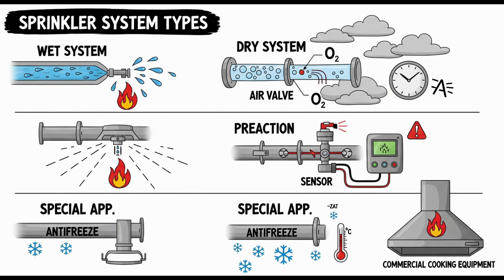Okay. The temperature rating of these pilot sprinklers detectors is selected based on the environment, just like regular sprinklers. Yes, the temperature rating is selected according to the criteria in section 9.4.2, which generally requires choosing a rating based on the maximum expected ambient ceiling temperatures in the protected area, ensuring they don't activate prematurely, but do activate reliably when a fire occurs. What about the maximum horizontal spacing allowed between these pilot detectors?